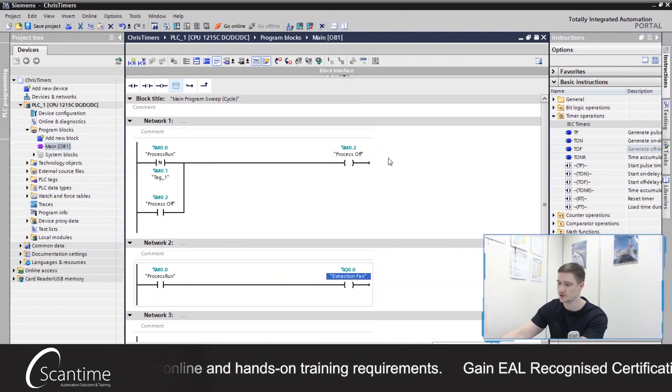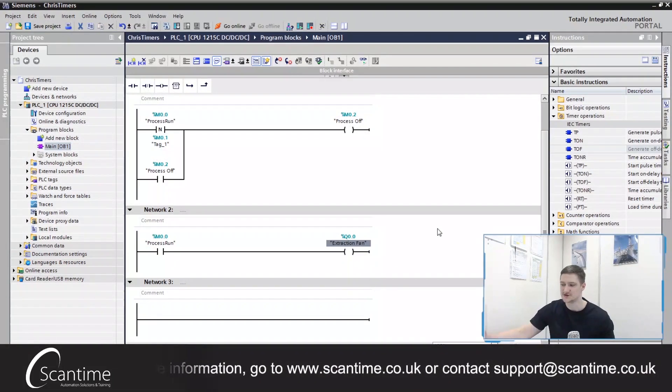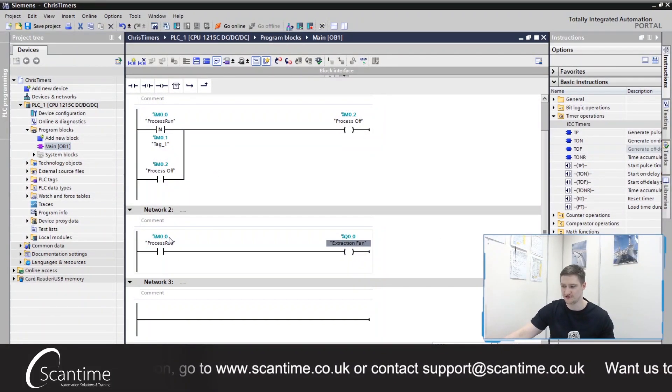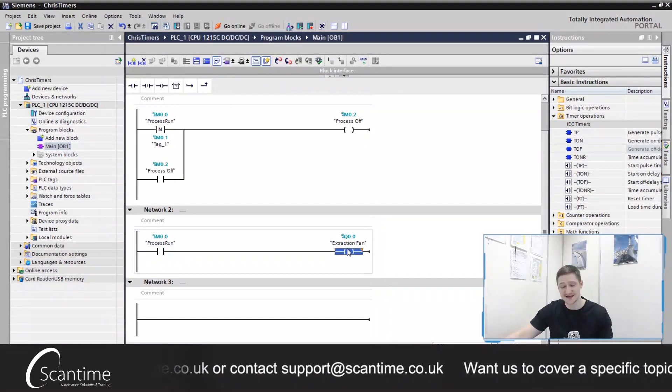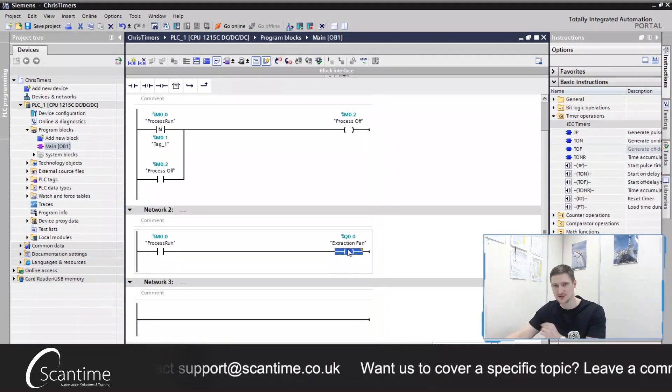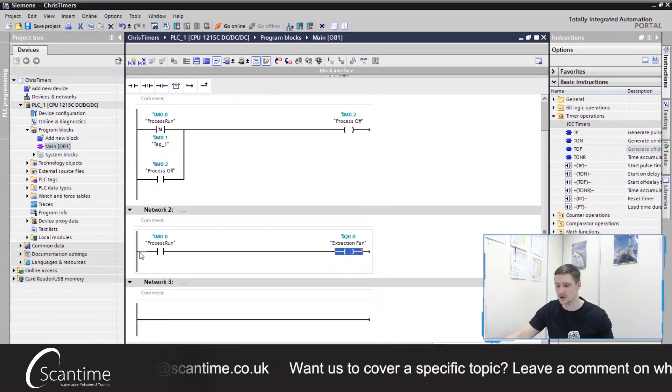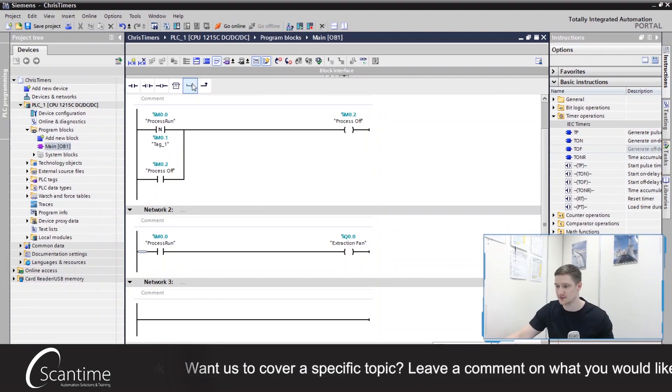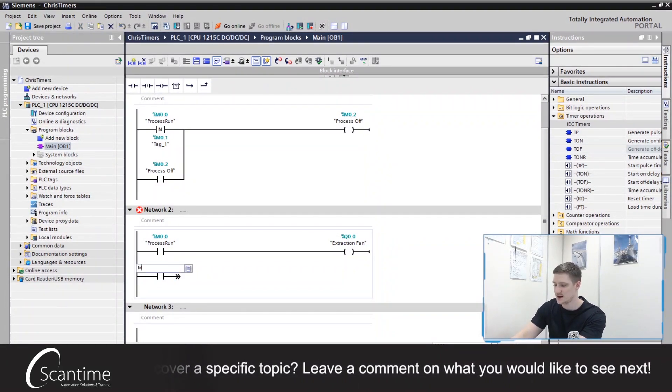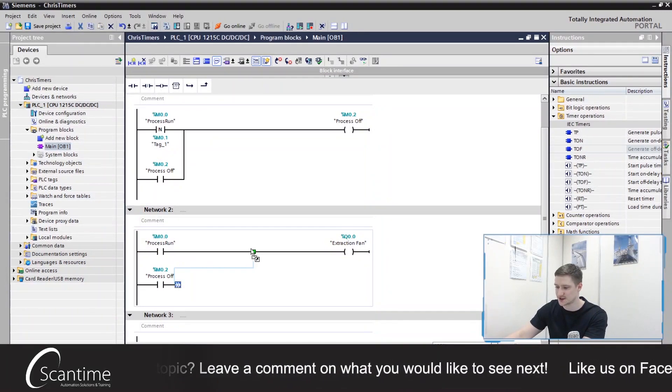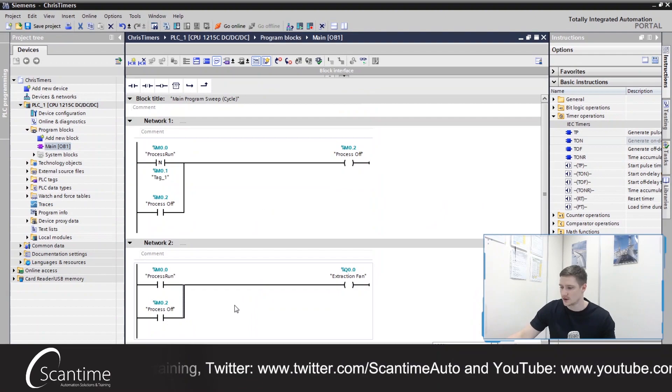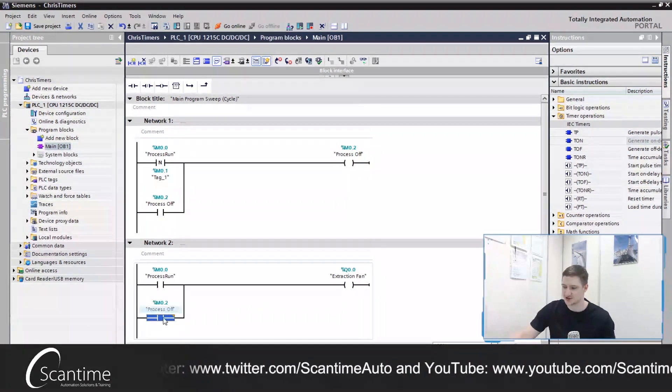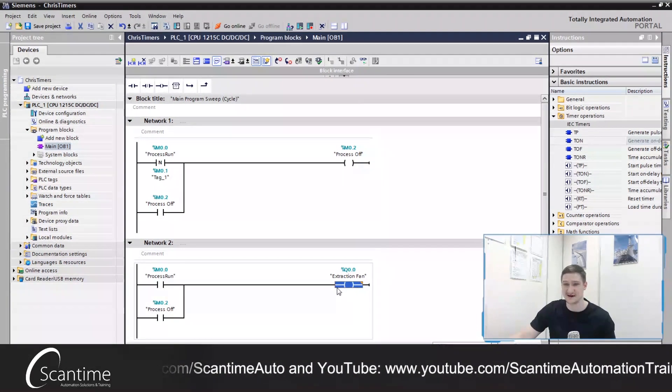So now what I need to do is when the process turns off, that means that this contact is also turned off. We need to keep this extraction fan running. So how can we do that? Well, what we can do is we can branch down from here and we can place in here M0.2 and branch that up to this chap over here. So that process off signal now keeps our extraction fan on.